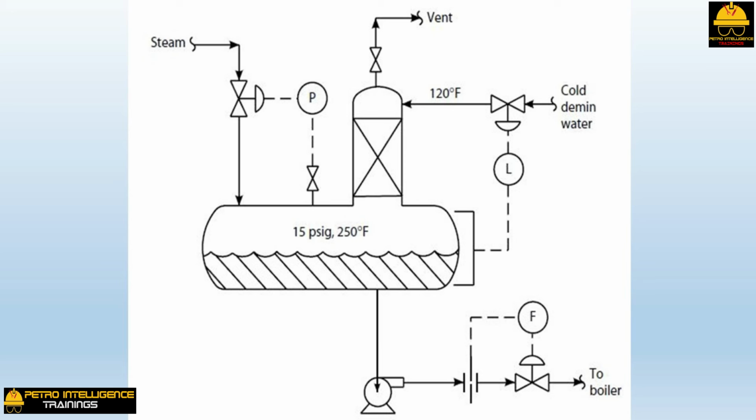Someone had the latter problem at the refinery. The refinery was spending a small fortune on the oxygen scavenger chemical, hydrazine. All the engineer did was to lower the deaerator set point pressure from 18 to 13 psig, and the residual oxygen in the effluent BFW dropped by an order of magnitude.